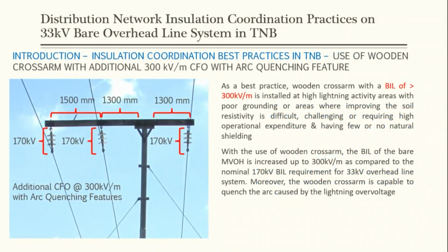The first best practice that we have been using so far is the use of wooden cross arm with an additional 300 kV per meter CFO, with arc quenching features. As a best practice, wooden cross arm with a BIL of more than 300 kV per meter is installed at high lightning activity areas with poor grounding, or areas where improving the soil resistivity is difficult, challenging, or requiring high operational expenditure, and having few or no natural shielding. When we talk about natural shielding, it can be high structures, it can be trees, for example, or even other power system structures or poles, such as transmission line towers.